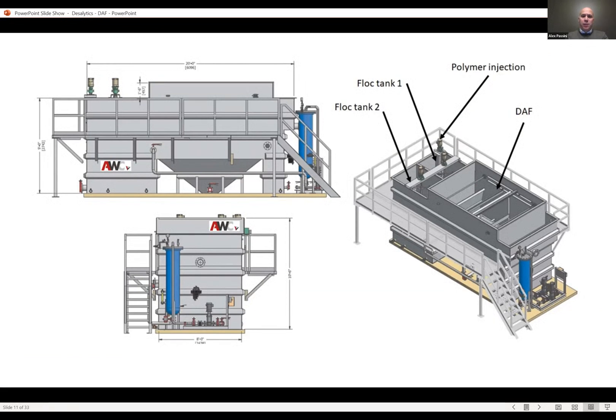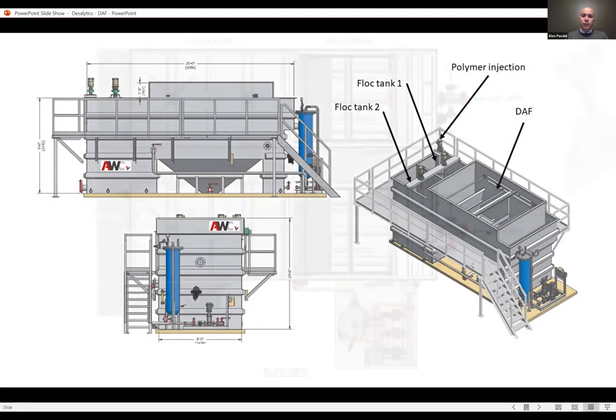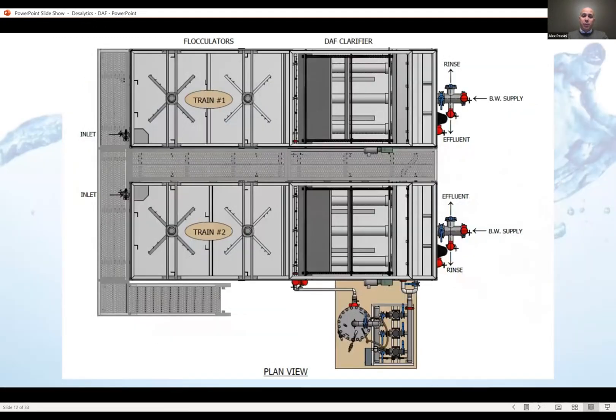This is a standard wastewater plant. When it comes to DAF, an interesting note: for wastewater DAF, you'll notice the floc tanks are smaller and the DAF cell is bigger. Whenever you're going with wastewater DAFs, you need less contact time for flocculation; however, your DAF cells are going to be running at much lower hydraulic levels. When we go to potable, you'll see significantly larger flocculation cells and a shorter DAF — more contact time in flocculation and less in the DAF. It's easy to see the ratio between one and the other.